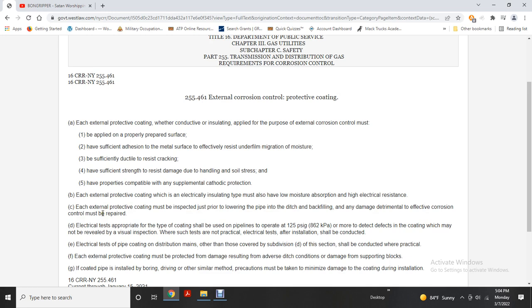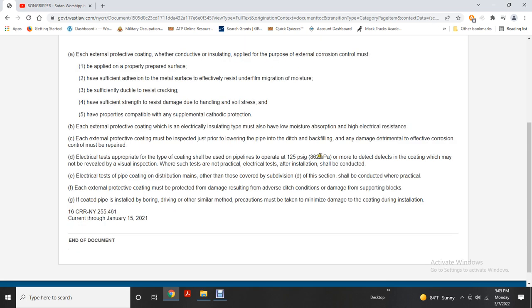An electrical test appropriate for the type of coating should be used. Pipelines operating at 125 psi gauge or above may require tests that detect coating defects not revealed by visual inspection. Where such tests are not practical, electrical insulation tests should be conducted. Each external protective coating must be protected from damage resulting from ditch conditions or supporting blocks. If coated pipe is installed by boring, driving, or other similar methods, precautions must be taken to minimize coating damage during installation.